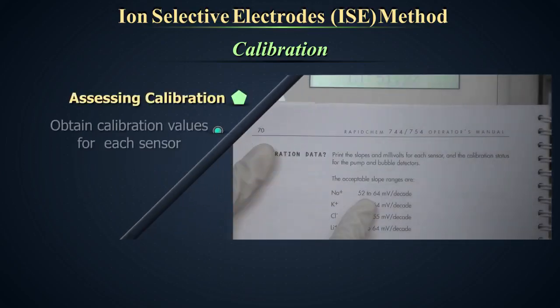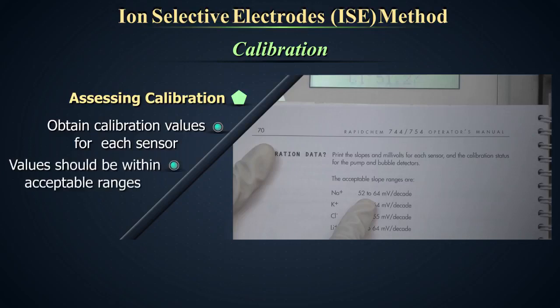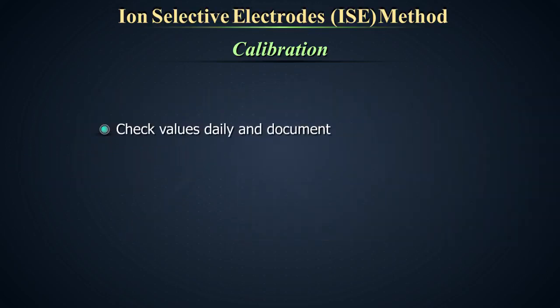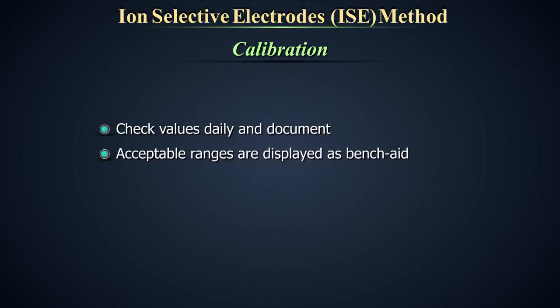Assessing calibration. The calibration performed by the machine is assessed by obtaining calibration values for each sensor. These values should be within acceptable ranges which are defined by the manufacturer. Check these values daily and document. Acceptable ranges should be displayed as a bench aid near the equipment to give ready reference to its performance.